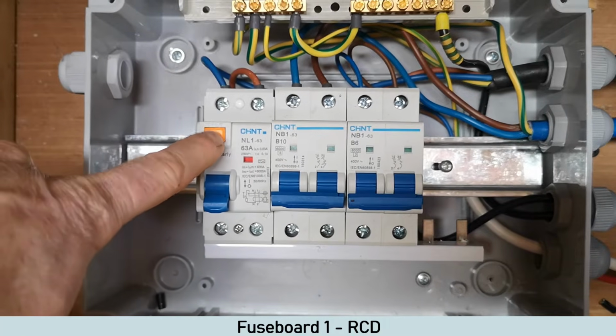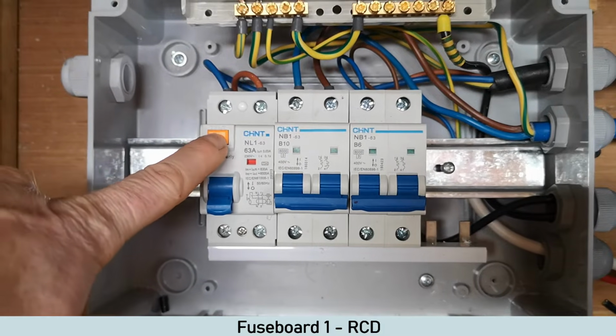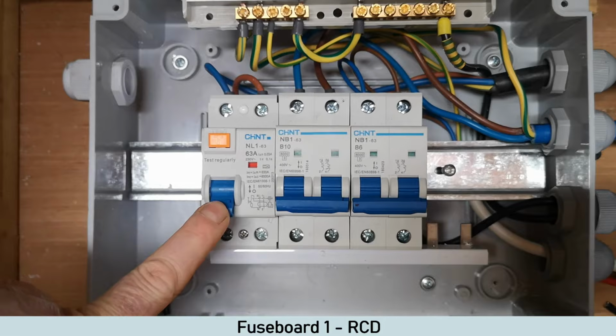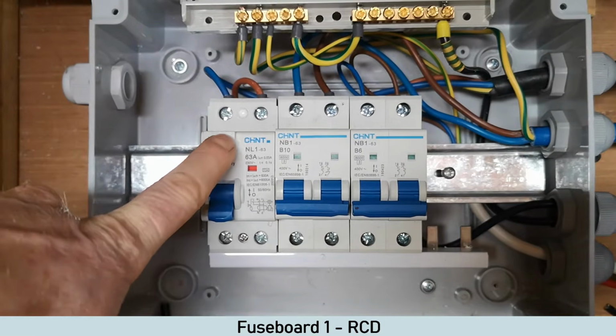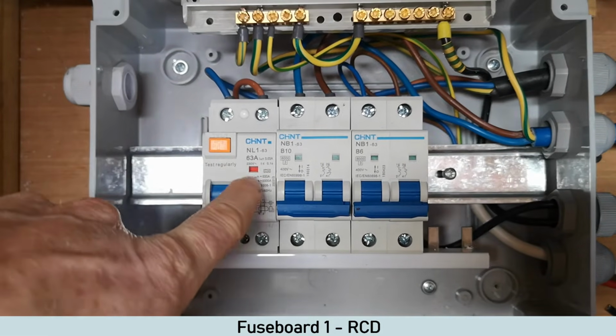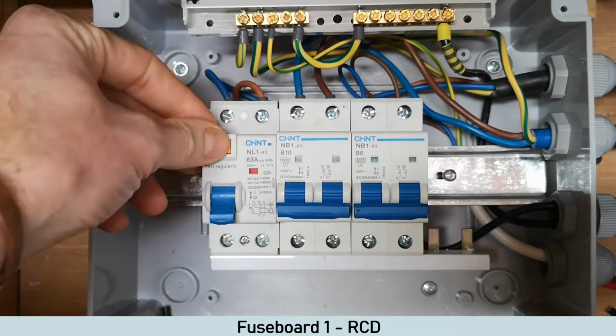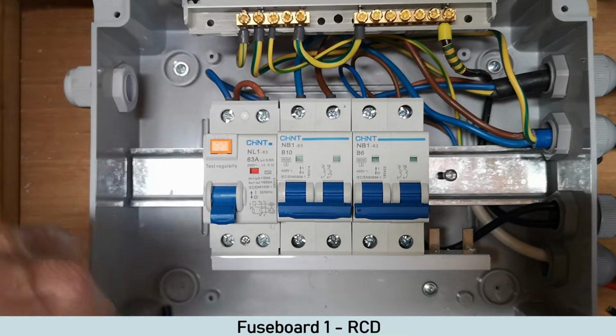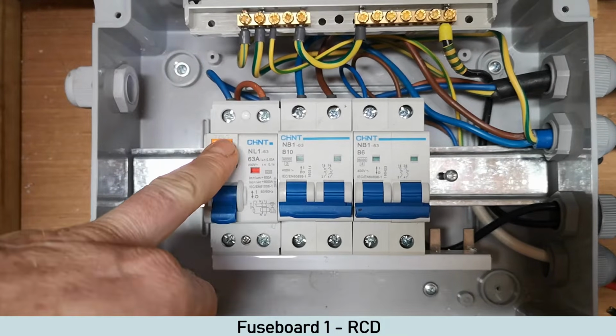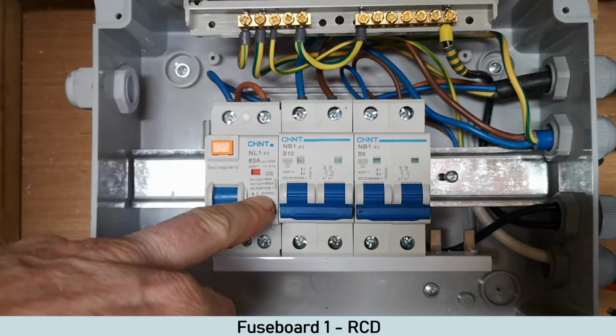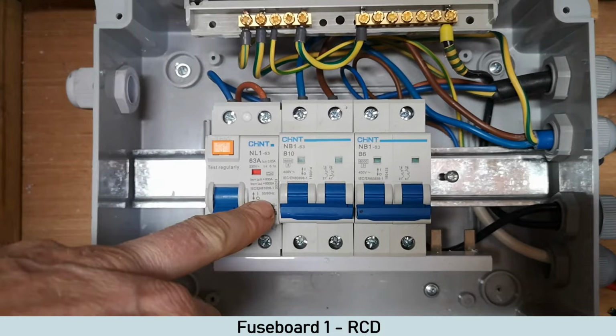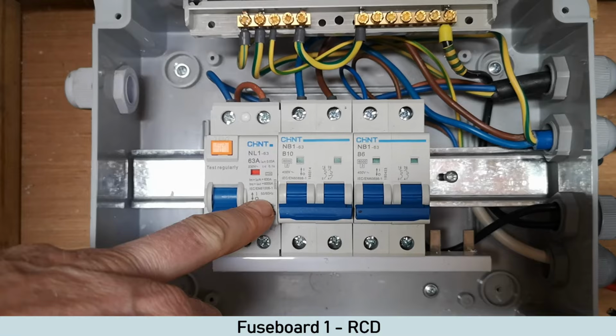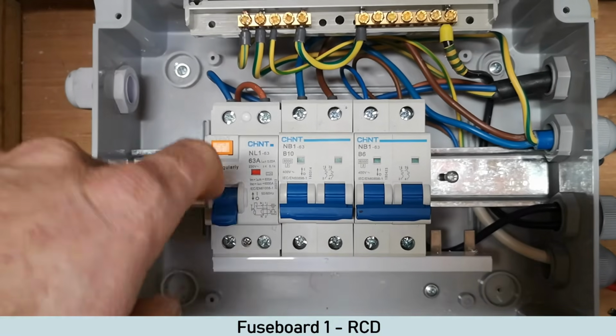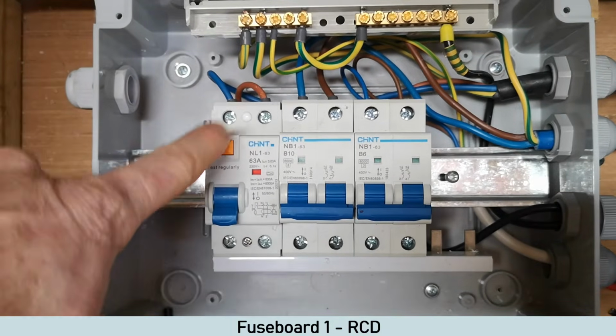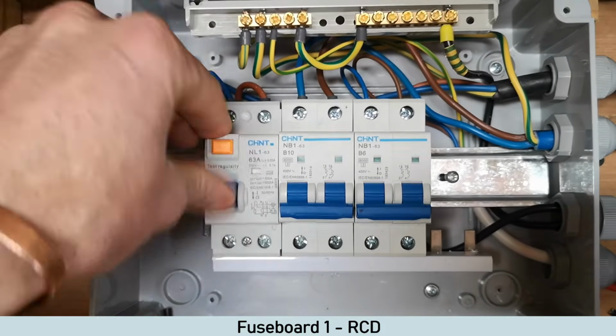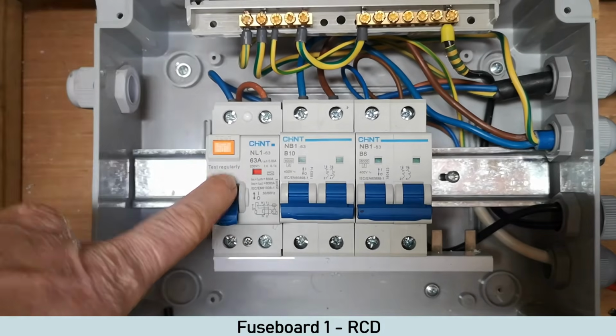Now this test button here doesn't necessarily mean that this RCD is functioning correctly. What the test button does is just test the mechanism inside. So obviously that's working, happy days. And what you should do is test that every month, because they have been known to seize up, and it can affect the tripping current as well. So every month put a reminder just to go press, and that's all you need to do. Do it a few times just to sort it out a bit.